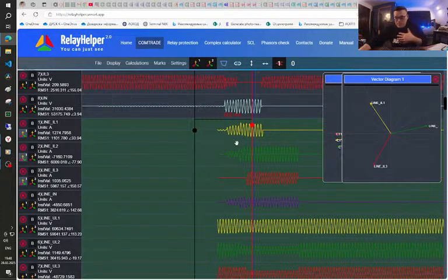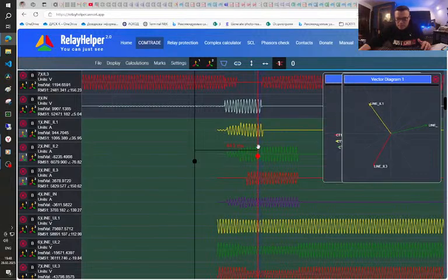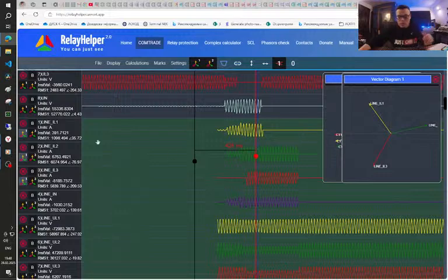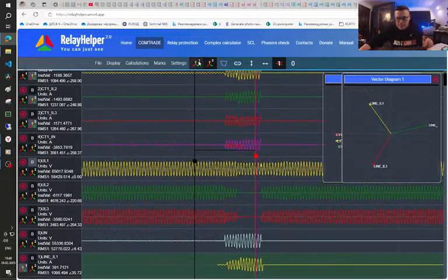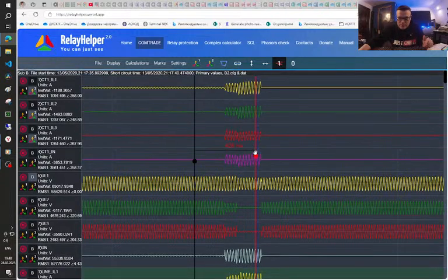I want to remind myself that on the top with this green background we can see the record from substation A. So this means that from this point there was also a two-phase short circuit, and here from the substation B perspective we also see the currents in phases B and C, and I want to draw your attention that the voltage is a little bit lower, but it is also 65 kilovolts, so it's like a healthy phase.